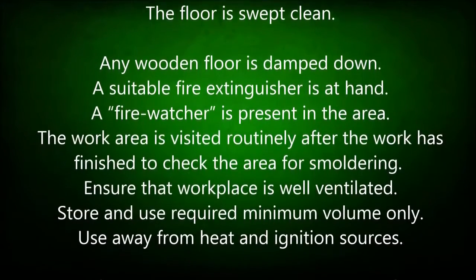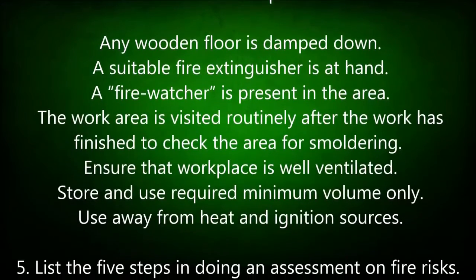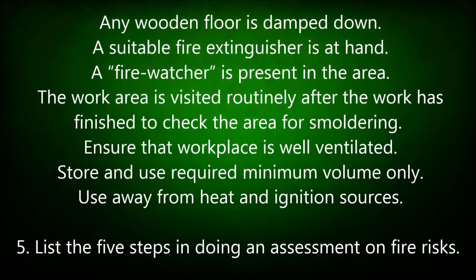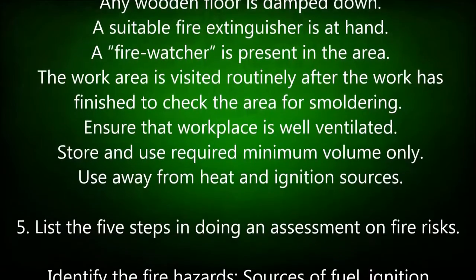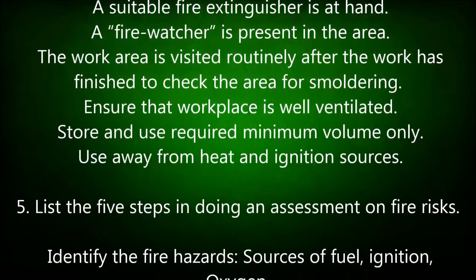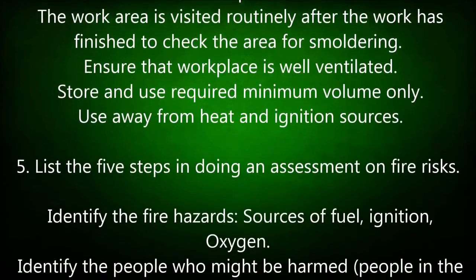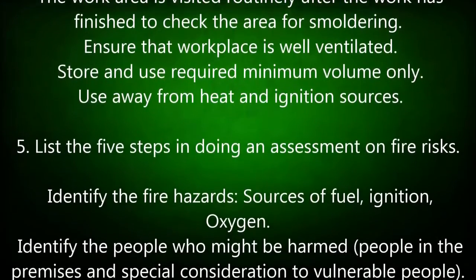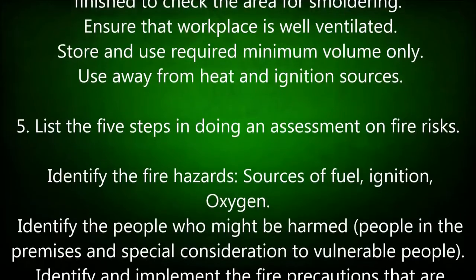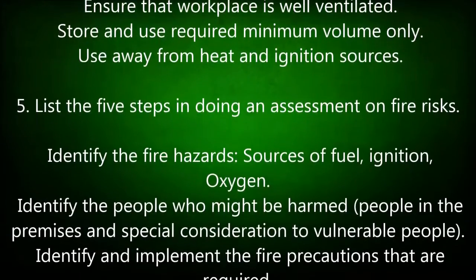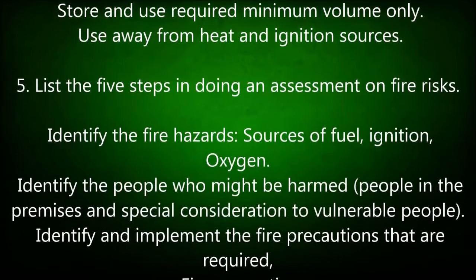5. List the 5 steps in doing an assessment on fire risks. Identify the fire hazards, sources of fuel, ignition, oxygen. Identify the people who might be harmed, people in the premises and special consideration to vulnerable people. Identify and implement the fire precautions that are required.